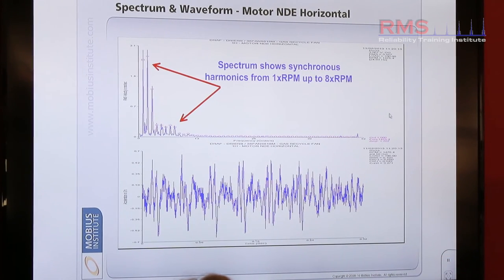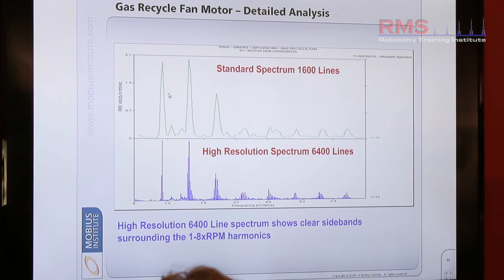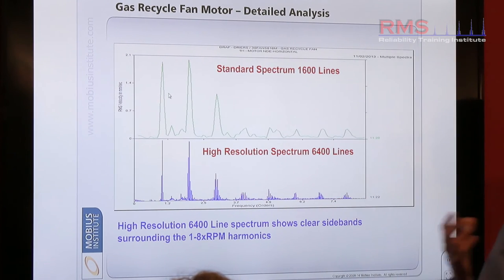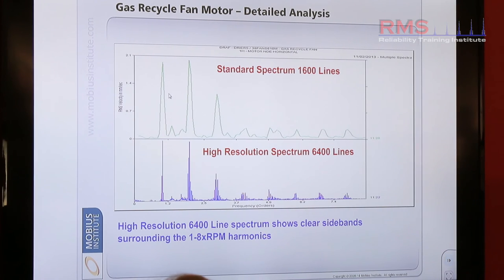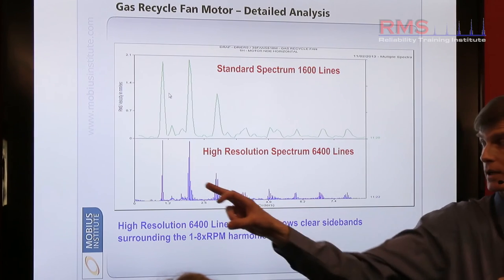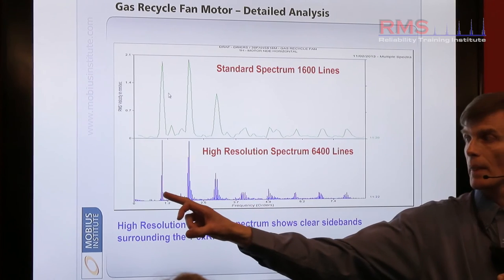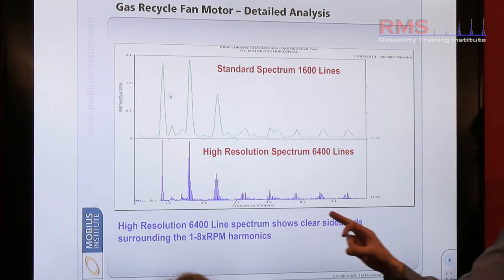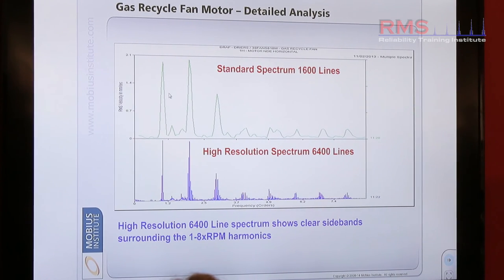So there they are in a bit more detail. We zoomed in and just taken that one spectrum out. Upon further investigation, we took a higher resolution measurement — like on your digital camera, you take more pixels. If we take more lines, we get clearer, sharper, crisper peaks. And it revealed that we had harmonics — equally spaced peaks — and equally spaced peaks either side of a central peak. So we had harmonics and sidebands, which fits with what we discussed before.